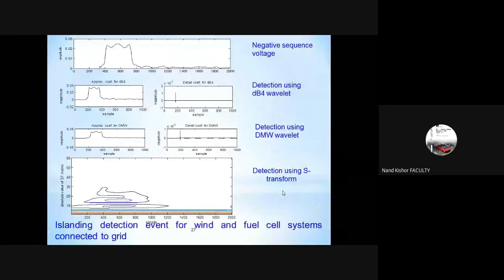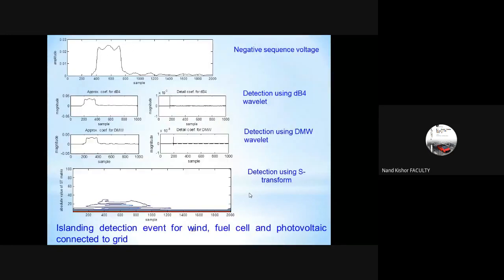And if you have a combination of generation systems, so we have a wind and the fuel cell, this is the variation of the negative sequence component and the detection using the mother wavelet and using the S transform. They have been reliable even for these hybrid combinations in the system. And if you have all three in combination, here is the variation of negative sequence components and detection using the mother wavelets and using the S transform. So even in the hybrid systems, the detection using these techniques has been reliable and accurate for islanding.